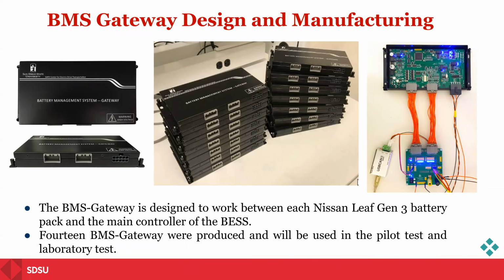In order to use this battery effectively in an energy storage system, we have to develop a BMS gateway. The reason is that each battery pack comes with a BMS, and we can read the data on it. However, this BMS sends out a CAN message which contains the battery information with the identical ID from each battery pack. Therefore, we cannot simply connect them in a CAN bus. We designed this BMS gateway to read the BMS information, stamp it with a different ID, and then send this information to an energy management system so that we know which information belongs to which battery pack.